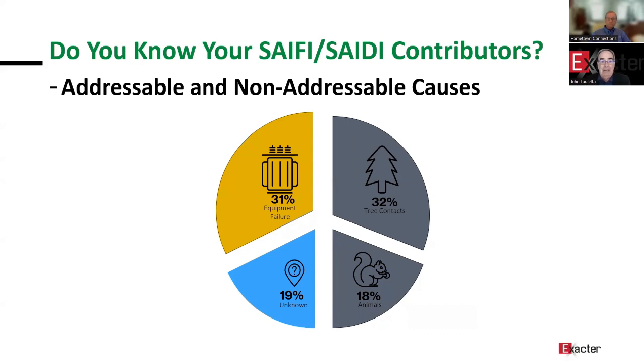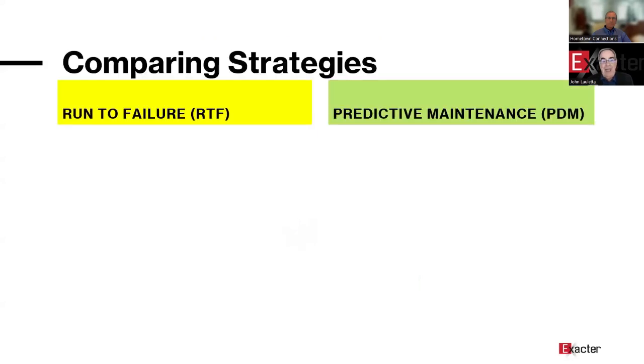Or if you see something like a broken cross arm or a cracked insulator or a loose conductor laying on the cross arm, those kind of things are the typical response to equipment failure. But we're going to get right down to what it is that has failed and how we can predict that it's going to fail and how we can then react to that prediction.